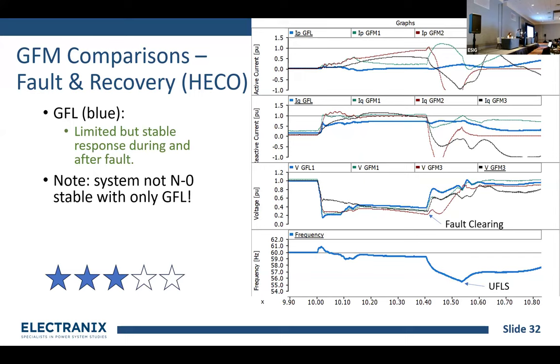The first device I'm showing is actually a grid following inverter, and it's behaving basically as well as we would expect a grid following inverter to behave. Active current is sitting at about zero before and after the fault, and it picks up a little bit afterwards in response to the low frequency on the system, but it's not giving us a lot of fast or voltage-like characteristic response — which is what we expect; it wants to be a current source. On the reactive current side, it's giving about 0.5 per unit injection, from K-factor controls. For a grid following device, three stars out of five, not too bad. But before we say this looks pretty good and ask why we even need grid forming — know that this system is not small-signal stable without grid forming. Without grid forming, right from the start of the simulation you'll start seeing small signal oscillations.